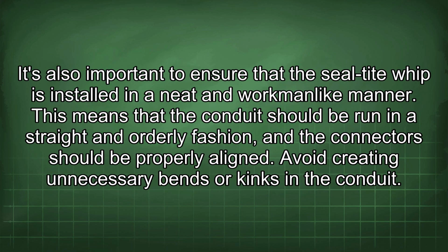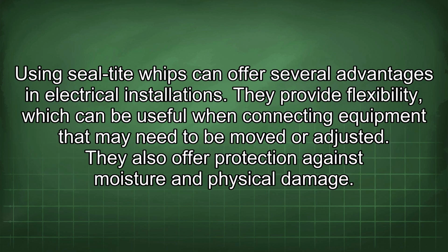It's also important to ensure that the Seal-Tite whip is installed in a neat and workmanlike manner. This means that the conduit should be run in a straight and orderly fashion, and the connectors should be properly aligned. Avoid creating unnecessary bends or kinks in the conduit. Using Seal-Tite whips can offer several advantages in electrical installations. They provide flexibility, which can be useful when connecting equipment that may need to be moved or adjusted.